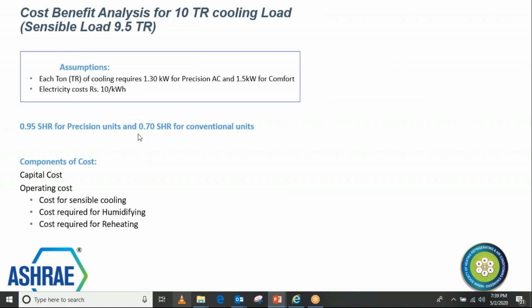This analysis is done to show you what we discussed a few slides before, how on paper these two technologies compare, and how much savings precision AC delivers when compared with a like-to-like comfort air conditioning system. We have taken an example of 10TR, for the sensible cooling requirement. You can see 0.95 sensible heat ratio for precision AC and 0.7 for conventional, although in most conventional units you may find around 0.65. So this is a fair comparison.